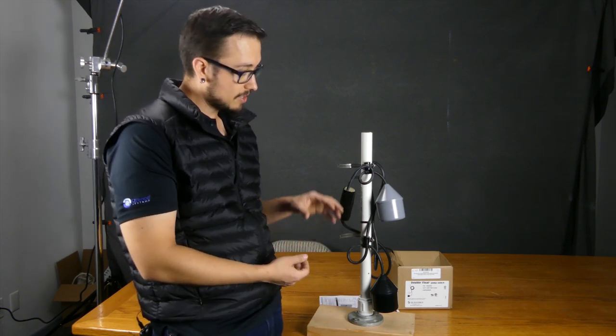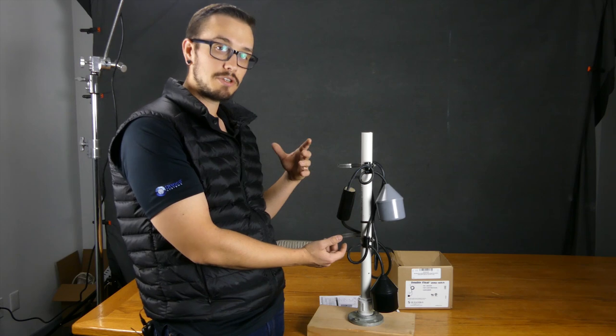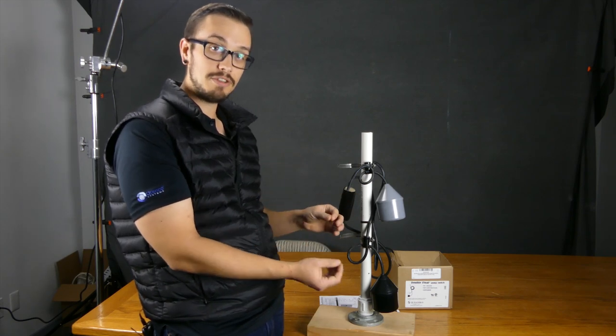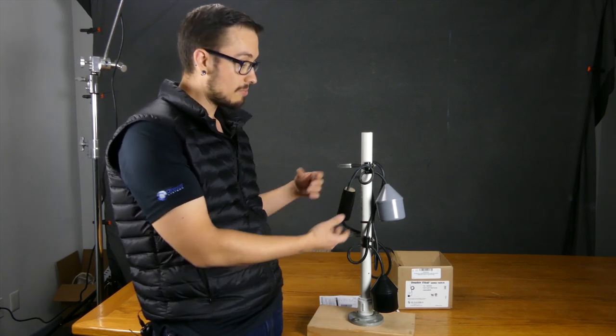The nice thing about these double float switches is you can actually get really tight with a minimum pumping range of 1.75 inches, which seems extreme, but you could stagger them, kind of one over here one over here, and have them really tight and really close.